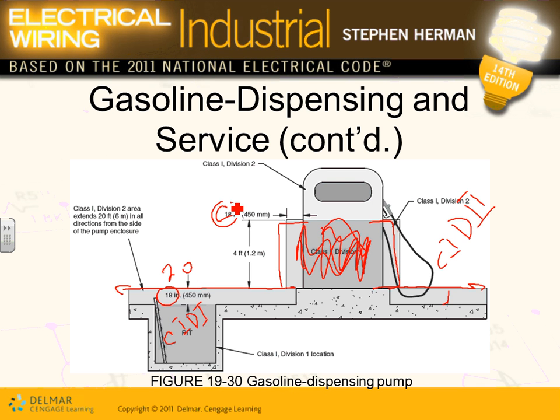When you put your light above the gas station, you can see that they all have to be enclosed. If the bulb were to fall or break or explode, would it go all the way down? No, it's contained. They have an enclosure. You can't have open bulbs like these. If you take that cover off and it explodes, it goes down, and down there in the gas station is a hazardous location. There could be a spill and it could ignite. Can you see the thinking when you do a gas station?